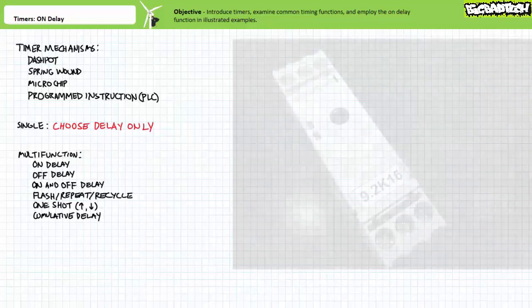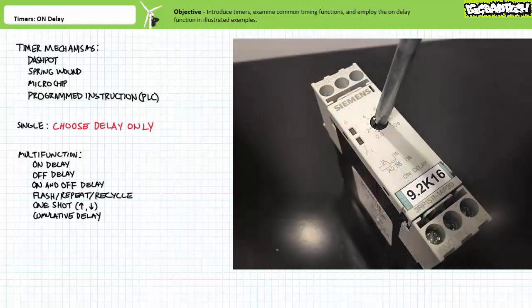Timers can be further classified into two general categories: single-function and multi-function. A single-function timer is normally inexpensive; however, as the name implies, it performs one function and one function only. To set up a single-function timer, a technician must choose a timer that executes the desired function and then adjust the delay period only. Here's an example of a single-function timer that performs only the on-delay function, with a delay period adjustable from 0.5 up to 10 seconds.